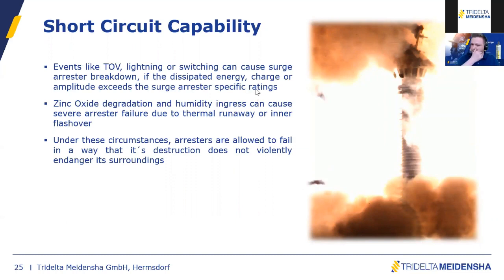TOV, especially when we talk about the energies that the surge arrester has to be capable of, can be a critical part when it's higher than expected. In cases where the surge arrester is selected for a grid that perhaps has a higher TOV than expected, or where lightning or switching impulses provide higher current densities or higher charge than expected, it can happen that the surge arrester is not capable of holding this voltage or current.